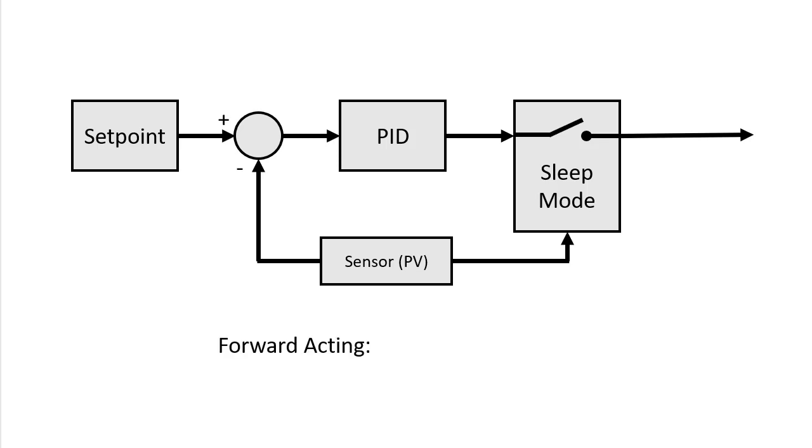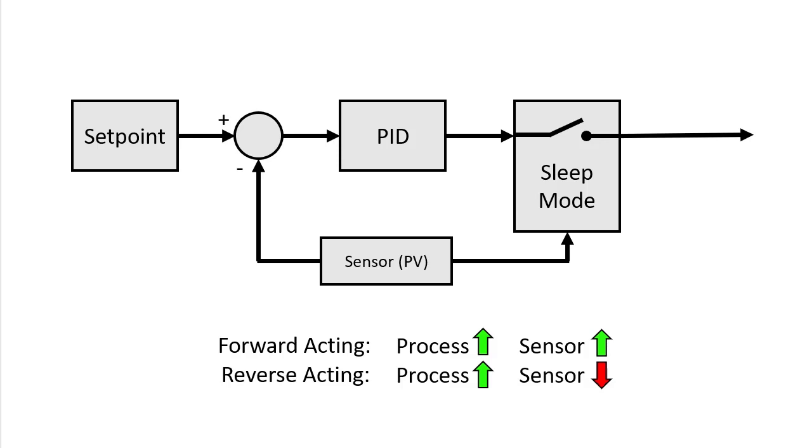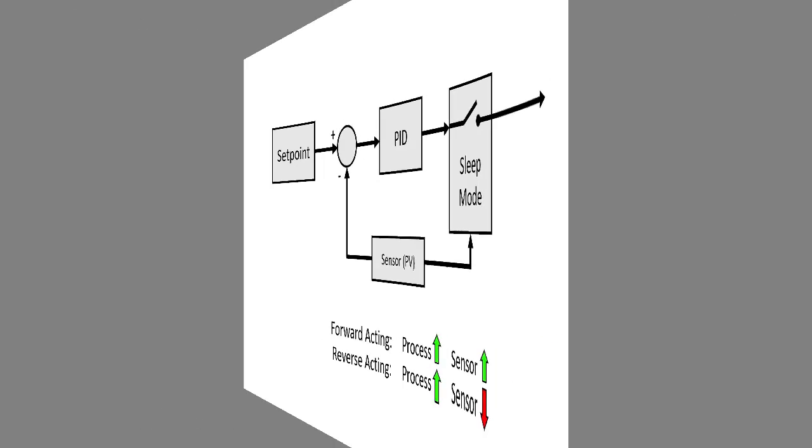Forward acting means as the motor runs and the water rises the sensor value also rises and that PID will automatically control the motor speed for us. Reverse acting is when the sensor value goes down as the water level rises. We'll do an example of reverse acting in the next video.